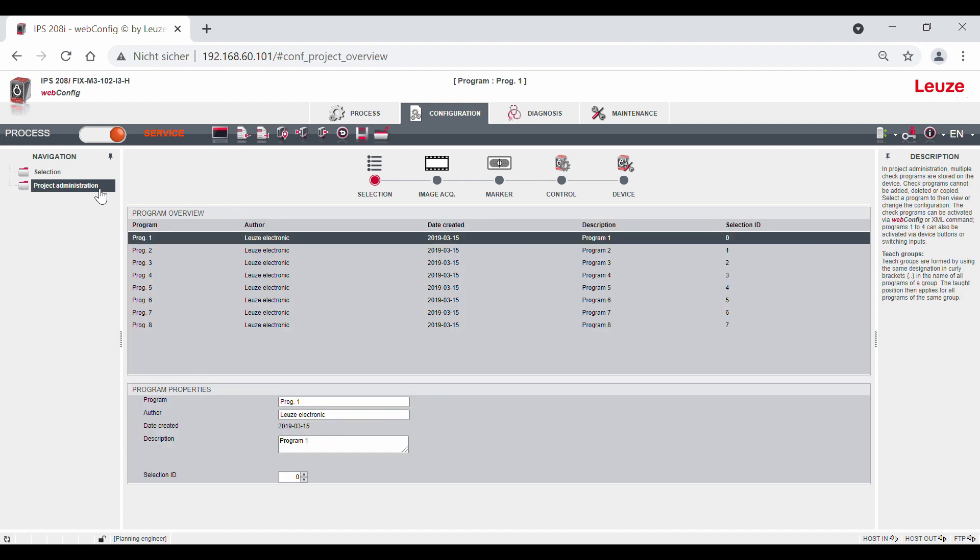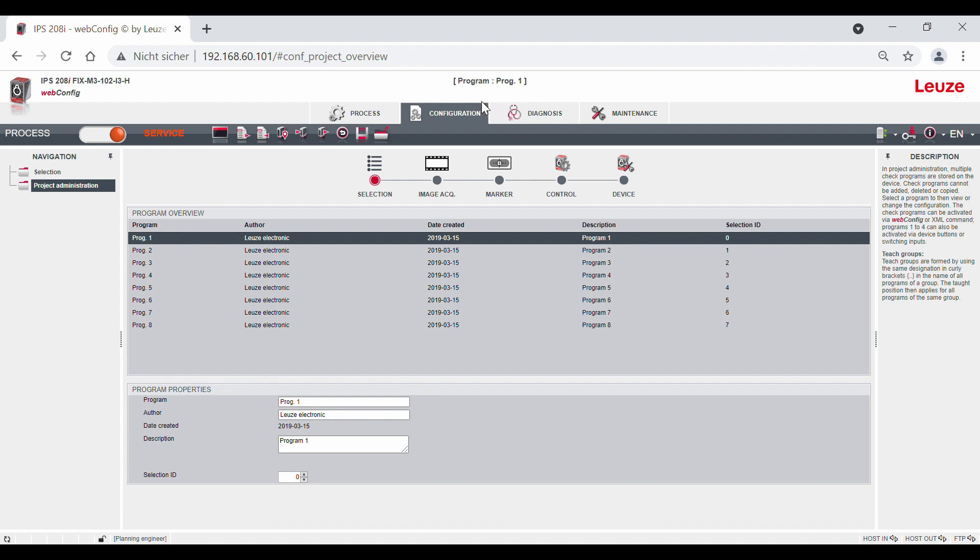You can select the current value program via the project management and it is displayed in the header. The switching of the programs in the process mode can be done either via two digital switch inputs or via the host interface, e.g. in PROFINET via module 6.1.